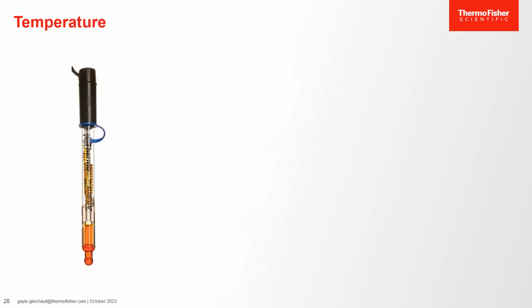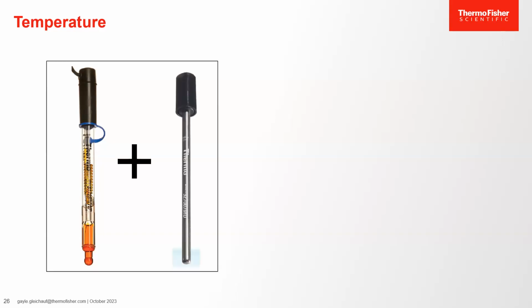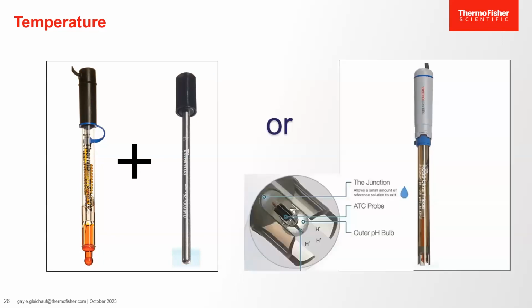For accurate pH measurements, we need to pay attention to the effects of temperature, because temperature affects the accuracy of both our calibrations and our pH measurements. Temperature effects are especially significant when sample temperatures are hot or cold. For measuring temperature, we can either choose to add a separate automatic temperature compensation or ATC electrode, or we can choose a pH triode, where the temperature sensor is incorporated into the electrode.